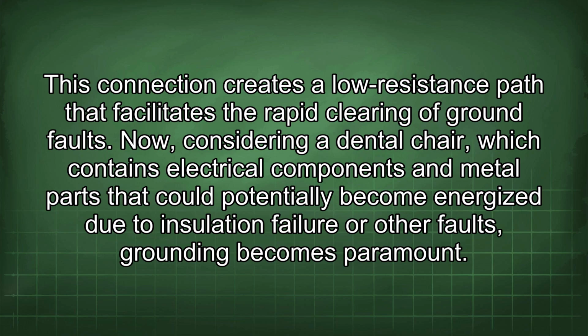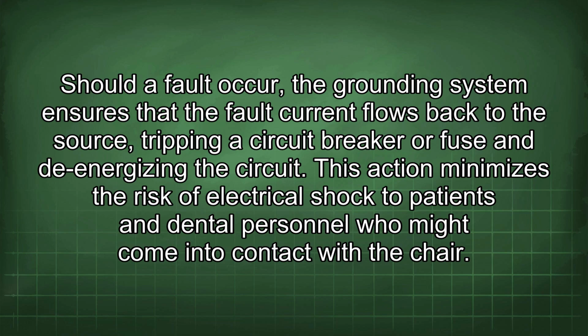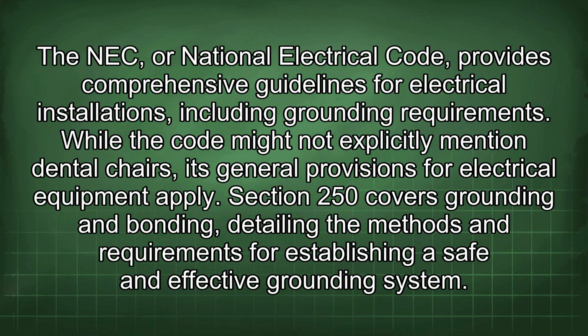Now, considering a dental chair, which contains electrical components and metal parts that could potentially become energized due to insulation failure or other faults, grounding becomes paramount. Should a fault occur, the grounding system ensures that the fault current flows back to the source, tripping a circuit breaker or fuse and de-energizing the circuit. This action minimizes the risk of electrical shock to patients and dental personnel who might come into contact with the chair. The NEC, or National Electrical Code, provides comprehensive guidelines for electrical installations, including grounding requirements.